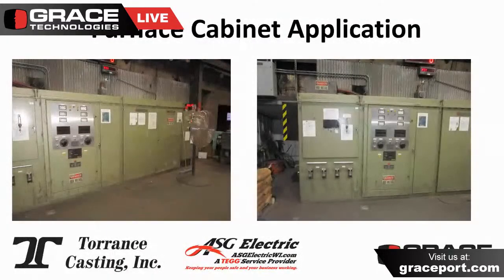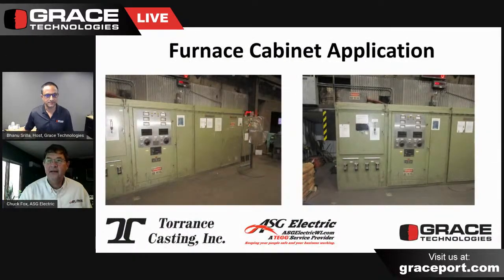So in review, this is one of the most critical assets for Torrance overall. It's unique because, looking at a one-line diagram, it goes from a medium voltage transformer right to this motor control cabinet, operating at 575 volts in the process. When we did the arc flash calculation, given how close it is to medium voltage and the type of fusing, the calculated incident energy was 119 calories, which compared to the 40 calorie threshold typically marking danger do not enter, puts us at almost 3x that level.